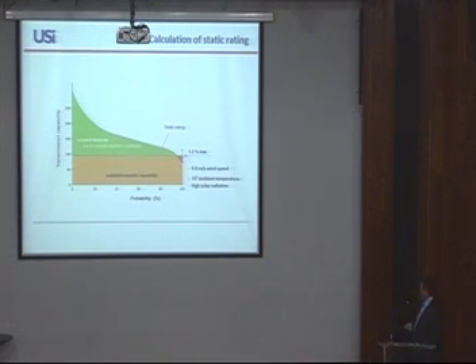But what you can see with that assumption is that there's a small risk, which is about 1 to 2%, because it might happen that you don't have this wind speed available, and if you have lower wind speeds, 0.4 or so, you run the risk that the real rating is even below the static one. This has been looked into for decades now, and there are only very rare situations where this really is a risk. For example, very sheltered lines running through forests, where the conductors are completely shielded by the trees, so no wind comes to the line. But in general, this can be considered as safe.